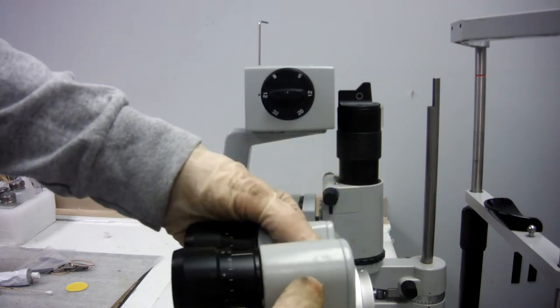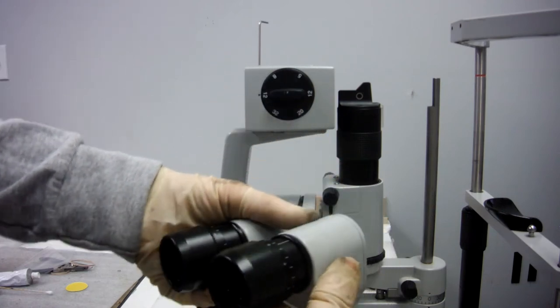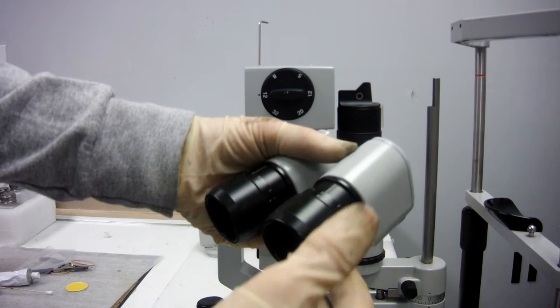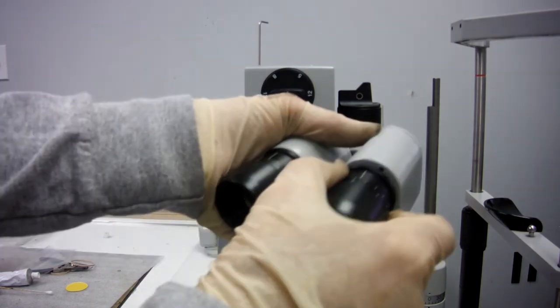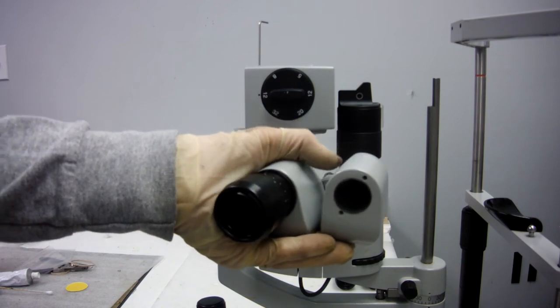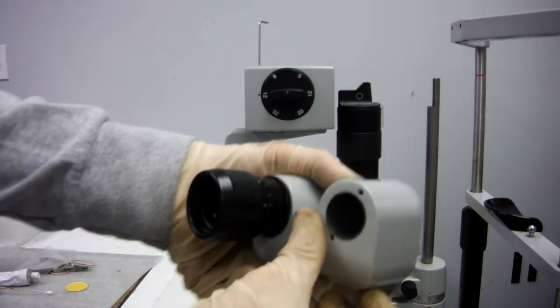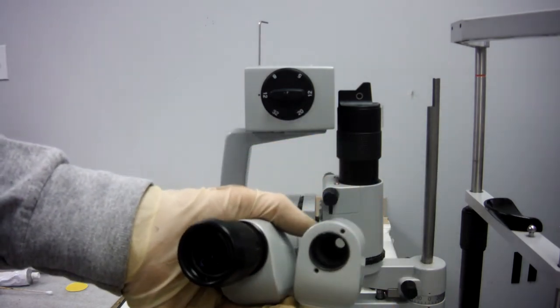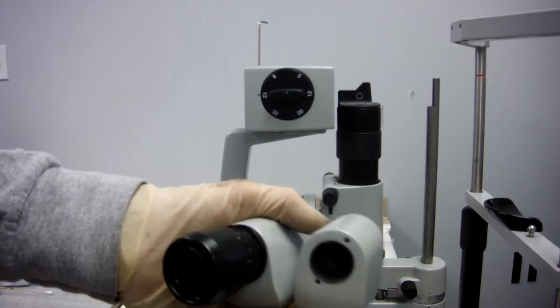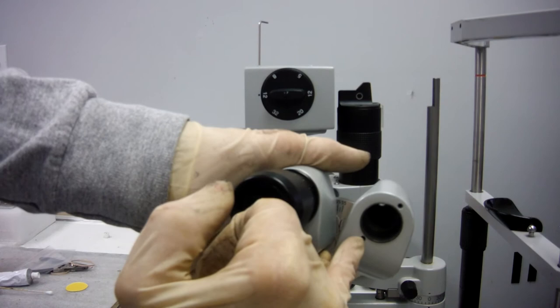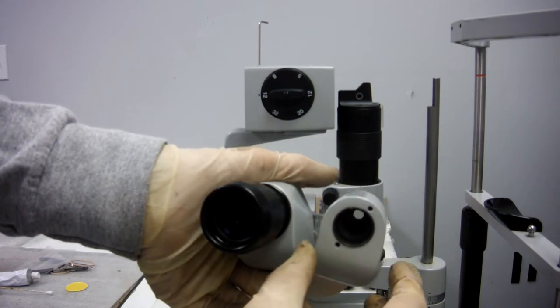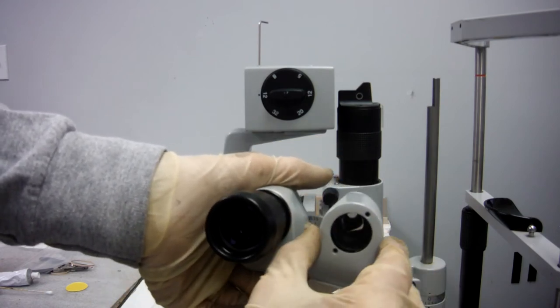But if you needed to go sideways, you'd have to go inside the head. Take out your eyepiece. There's two screws right here. Take the cover off.